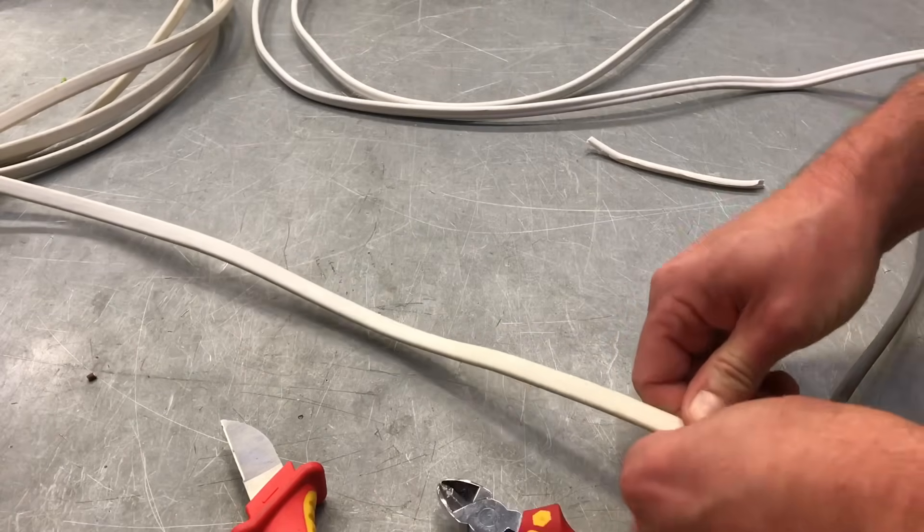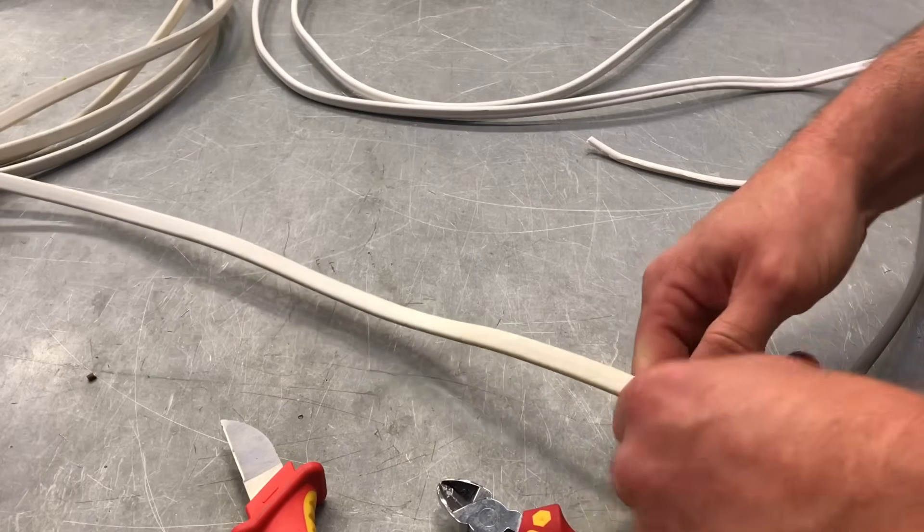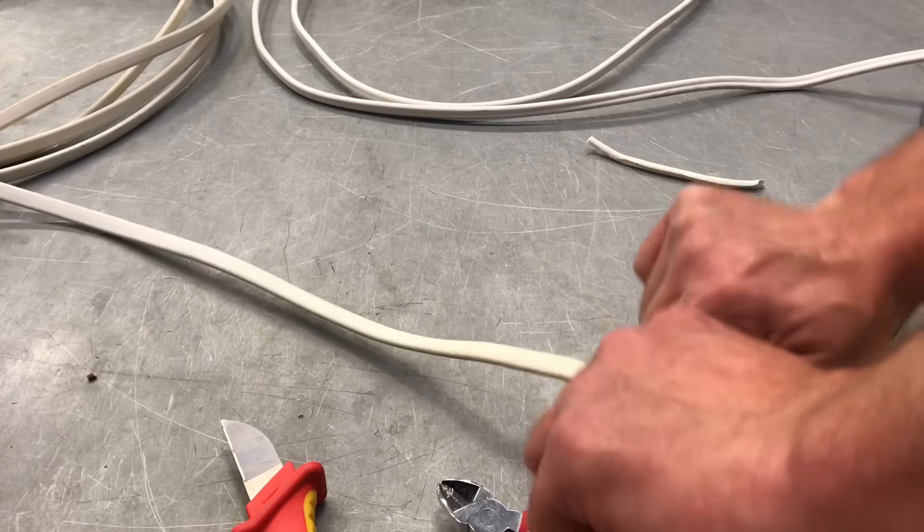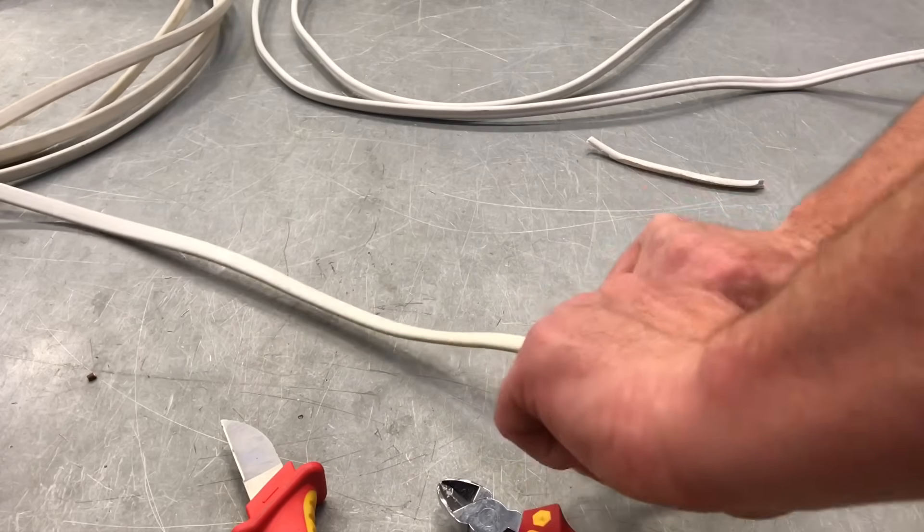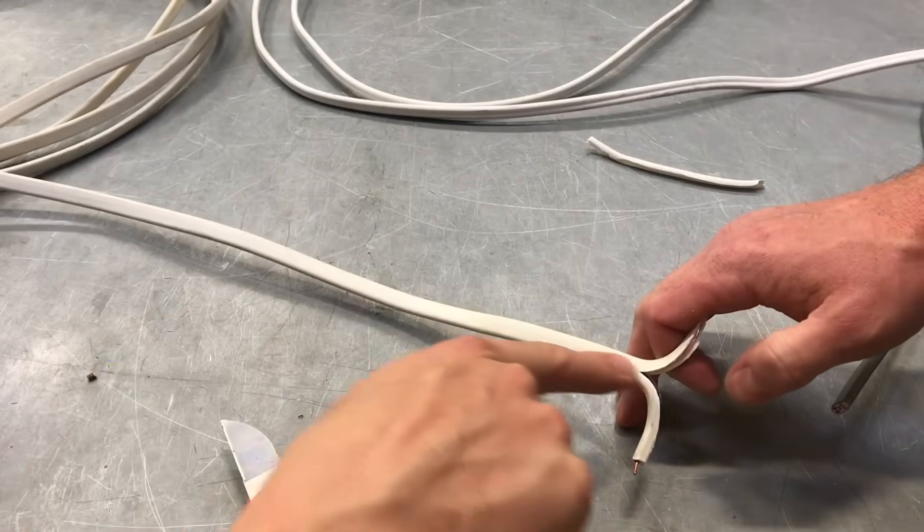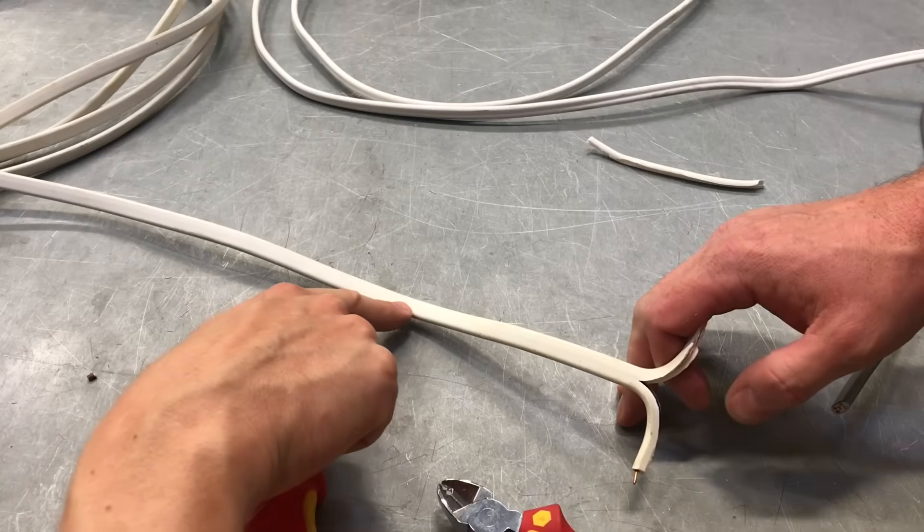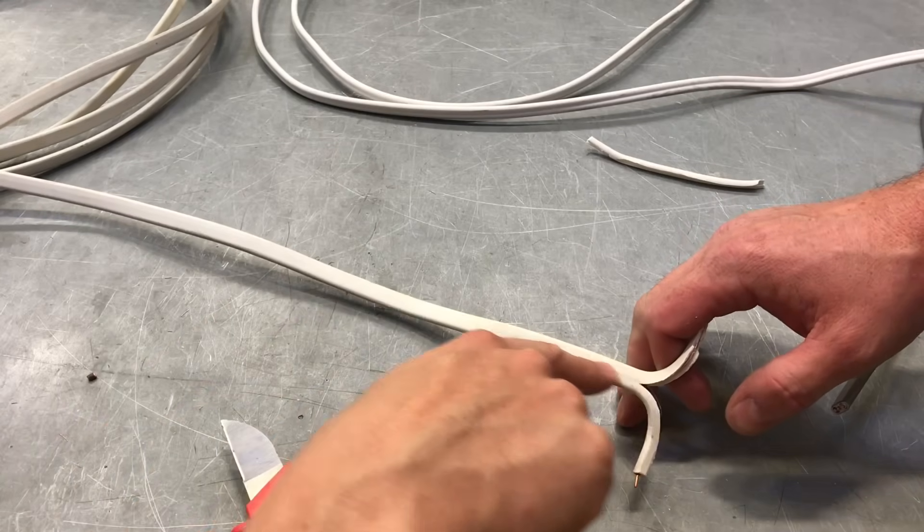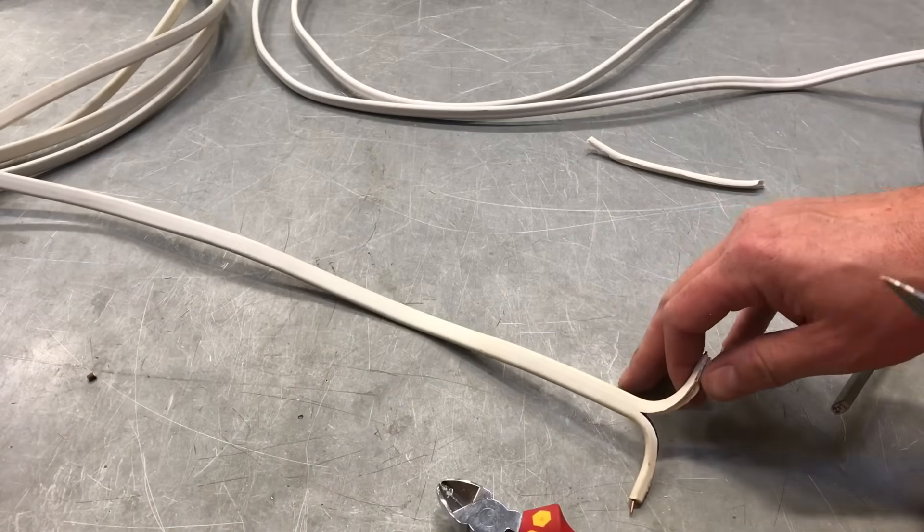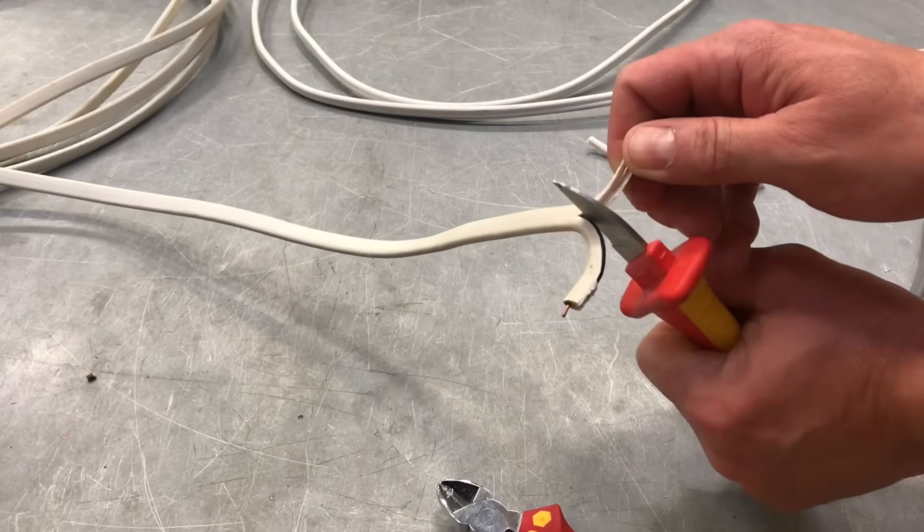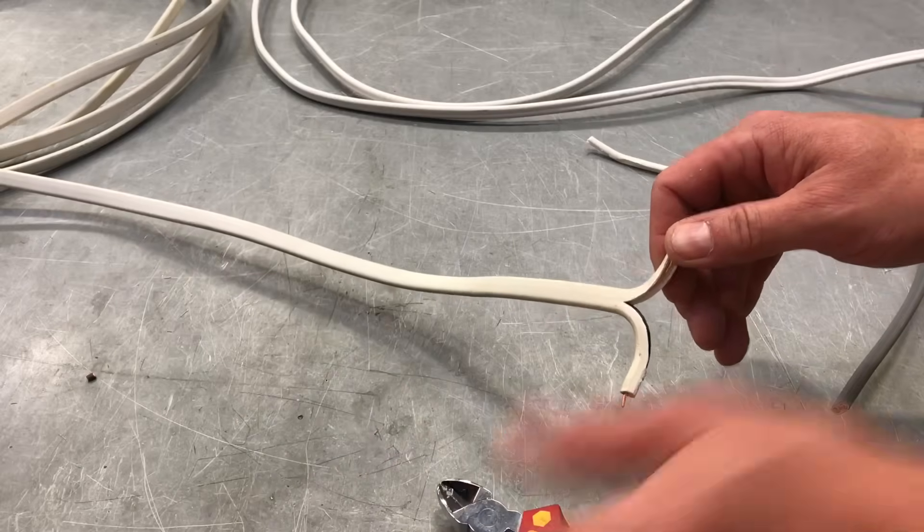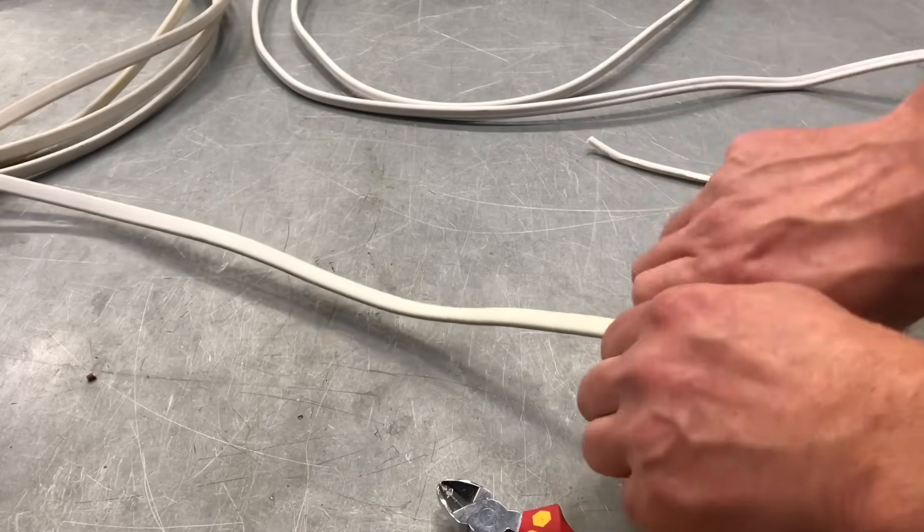and hopefully I can pull this apart. It's so easy. It's just sliding down there. And of course you could have run your knife down. I could. I could run down. Or even score it like we did before, but there's no indication that you might not be cutting into a live conductor though. You might have some serious issue there, whereas the groove in the other one just made sure that you kept just on the CPC track effectively. And again, I liked that technique and it was one I was trained with, but again, with our students coming straight from school, we're trying to avoid them running a knife down because it could damage the cable. So I think I've got it going now.